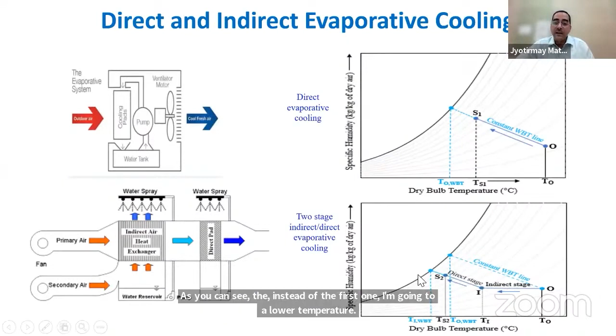So the advantage is twofold. One is you get more cooling. As you can see, instead of the first one, I'm going to a lower temperature, so I get more cooling effect. Another is I'm getting less humidity added in the air, because my first stage was without adding any humidity. Therefore, I not only achieve a lower temperature, I can have it perform during somewhat humid days also. And third, the most important thing for sustainability, I'm evaporating less water. About 30% less water consumption is there in this second type of evaporative cooler, the direct indirect evaporative cooler. So this adds to sustainability, and these options are now quite common.